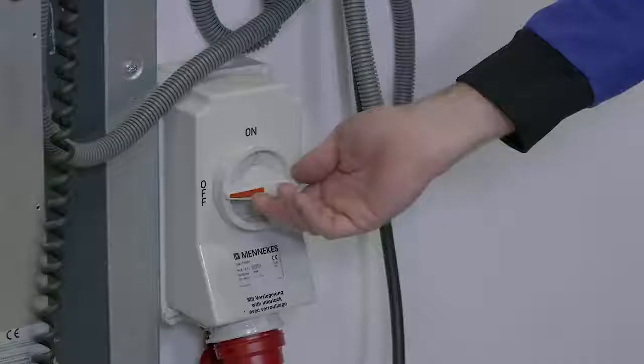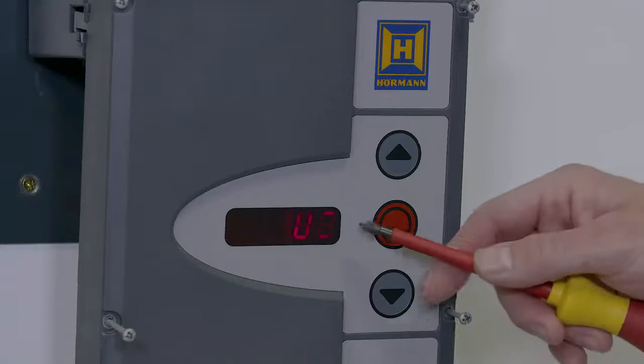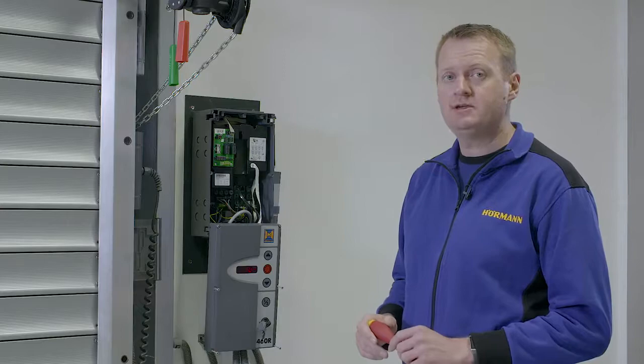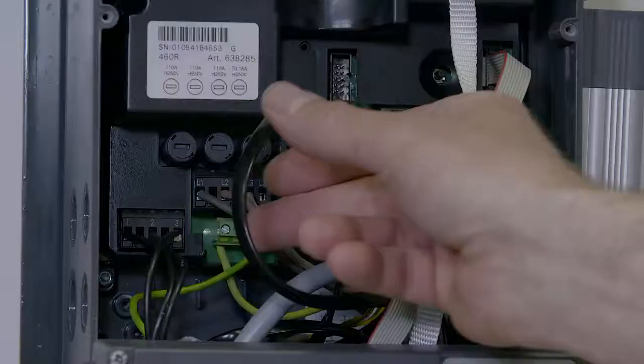We turn the power on and the display should show a U with a single line. If the display shows a U and two lines, please check the six core comms cable between socket X40 and the motor.